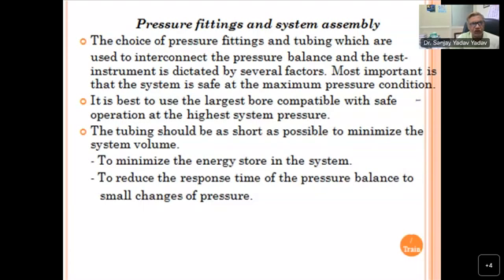For pressure fittings and system assembly, the choice of fittings and tubing used to interconnect the pressure balance and the test instrument is directed by several factors. Most important is that the system is safe at the maximum pressure condition. This is very important for the safety of the operator, the surroundings, and the instrument. It is best to use the largest bore compatible with safe operation at the highest system pressure. Use as much big bore tubing as possible. The tubing should be as short as possible to minimize system volume, to minimize the energy stored in the system and to reduce the response time. If your circuit is longer, your response time or sensitivity will be affected.